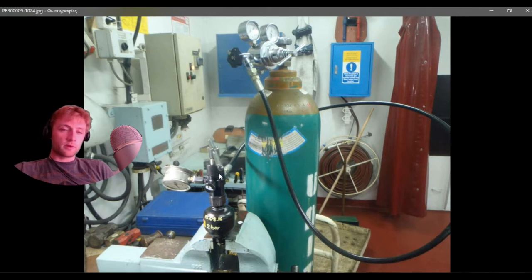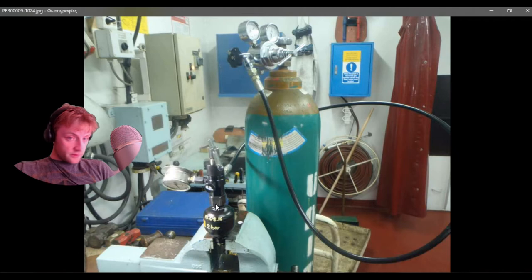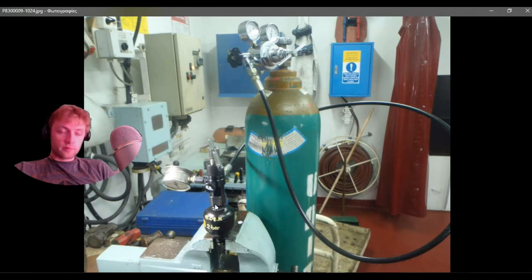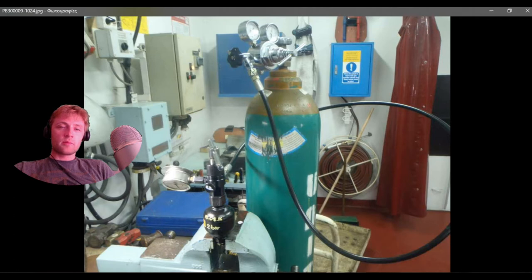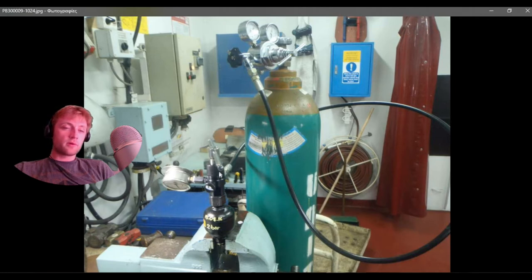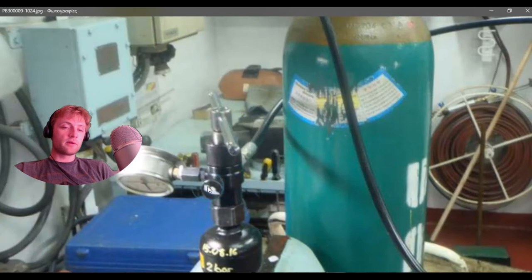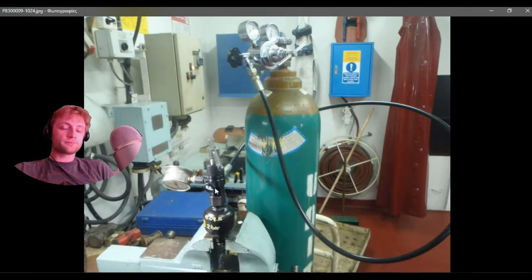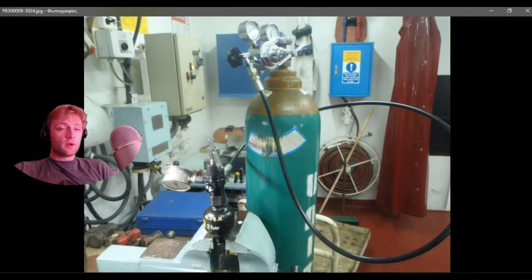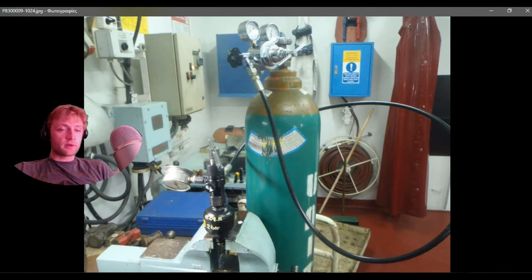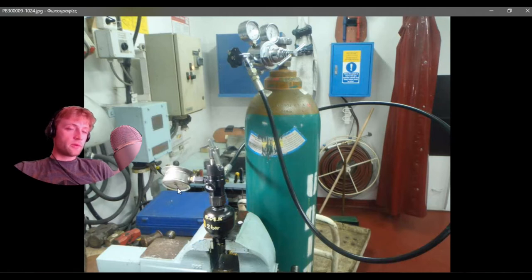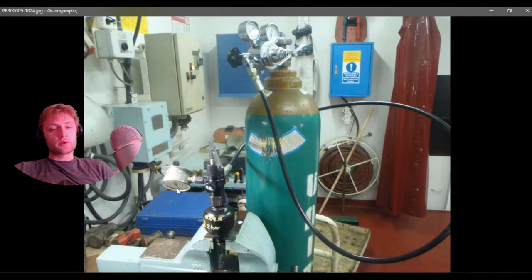You release this valve, this handle here counterclockwise to the left side. It's connected tight on the bottom. The pressure comes from the bottle, travels to the hose, and it remains here waiting until you open this valve. This small valve here, when you are opening it, the pressure gauge will indicate the pressure inside the accumulator.